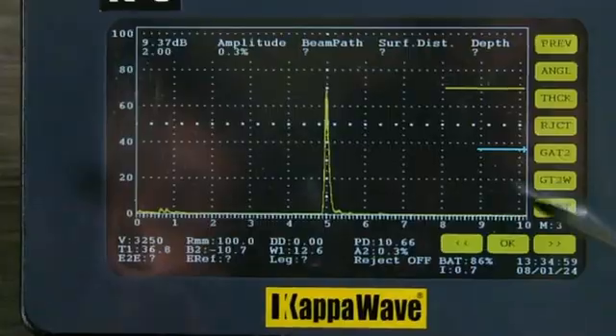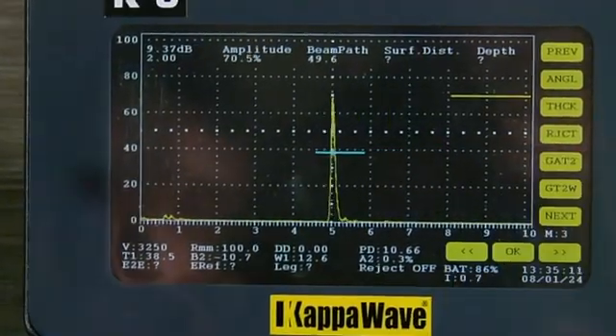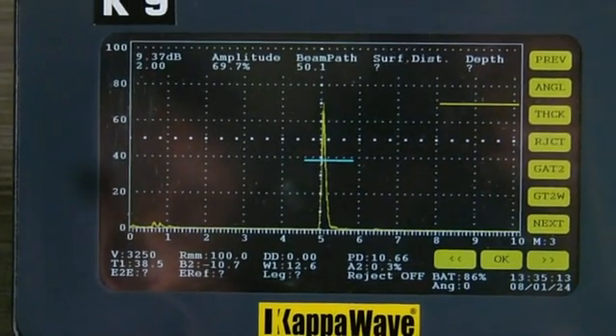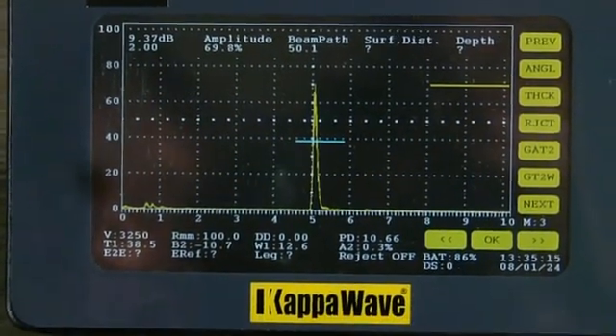If we turn towards the 50mm quadrant, then the signal should also come at 50. So this is one way to cross check the calibration.